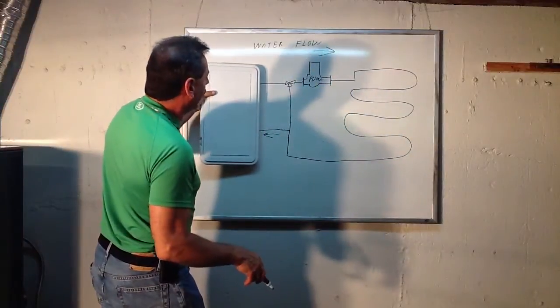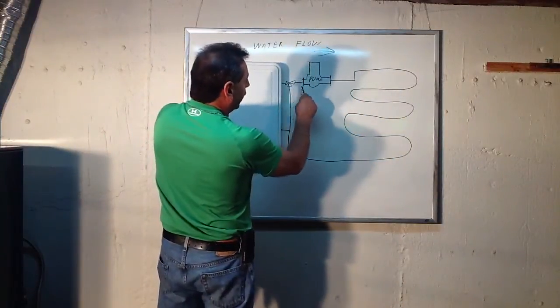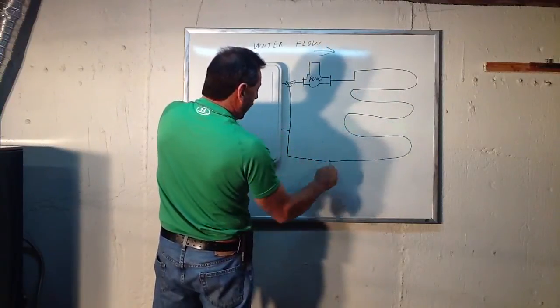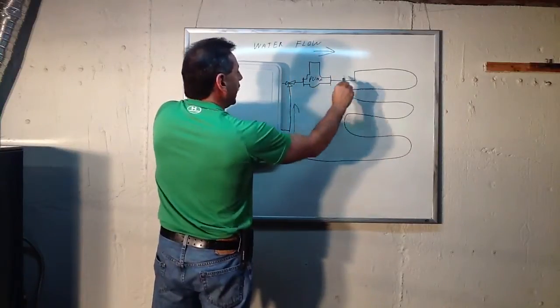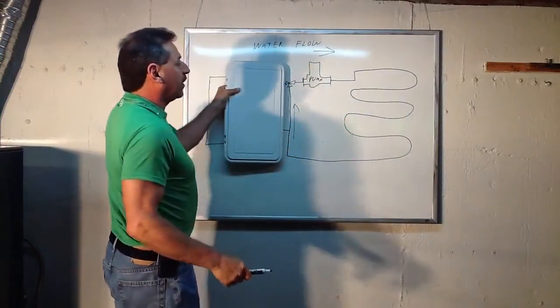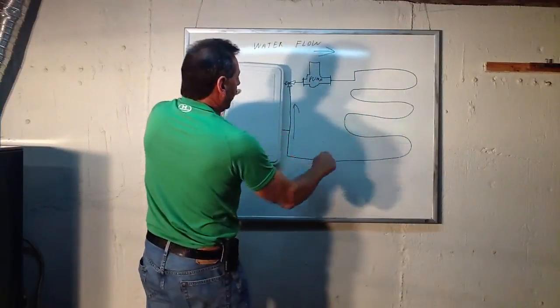Now the flow is from the boiler through the pump through the floor and back up to the mixing valve again. And now it's circulating that 135, 130 degree water around without the boiler. It just continues doing that, warming up the room until the water starts losing its temperature.